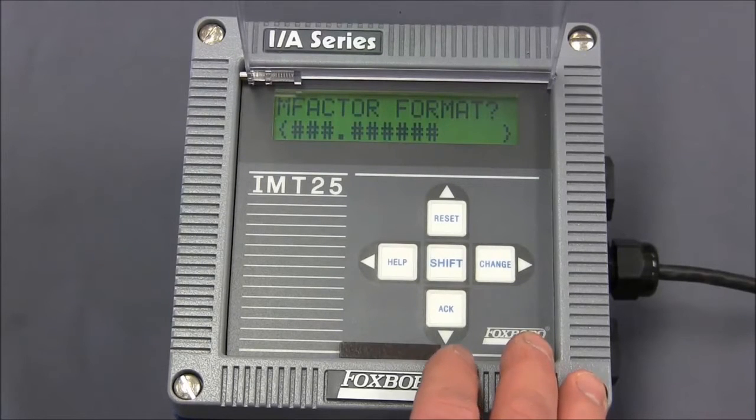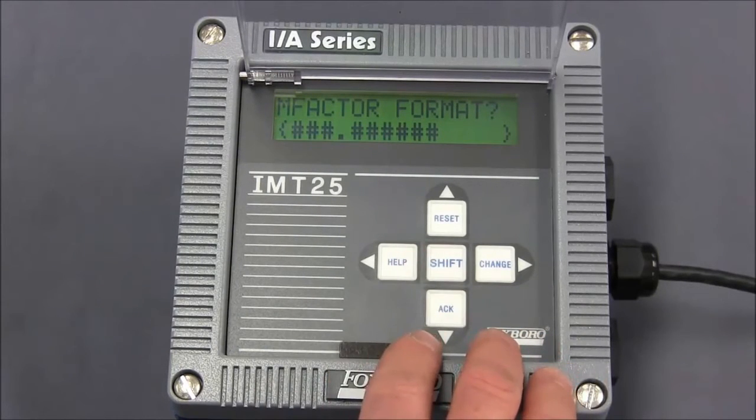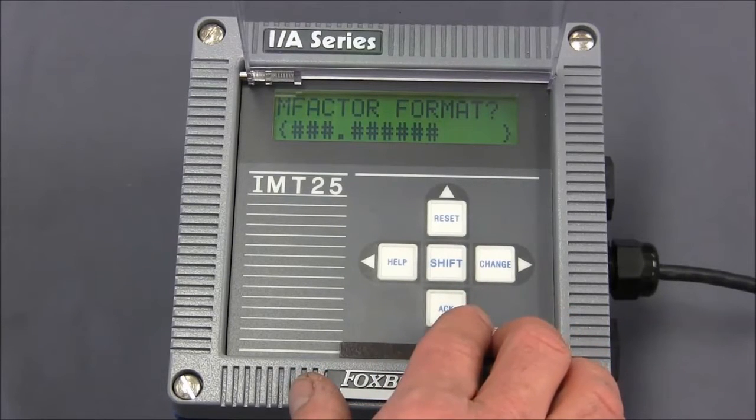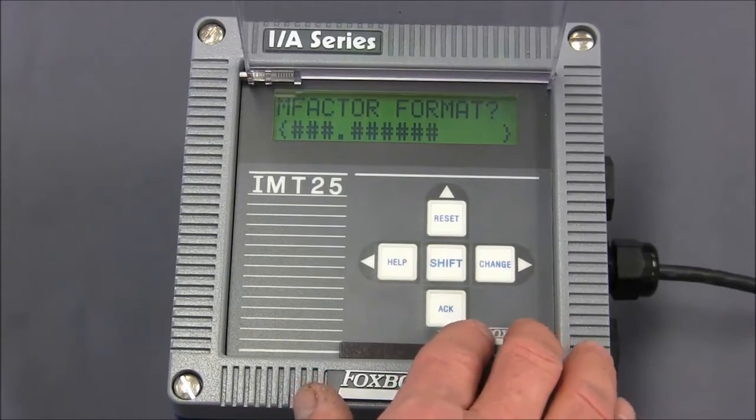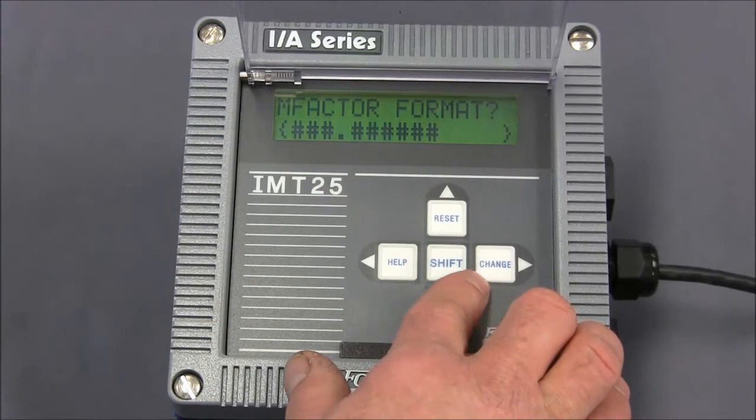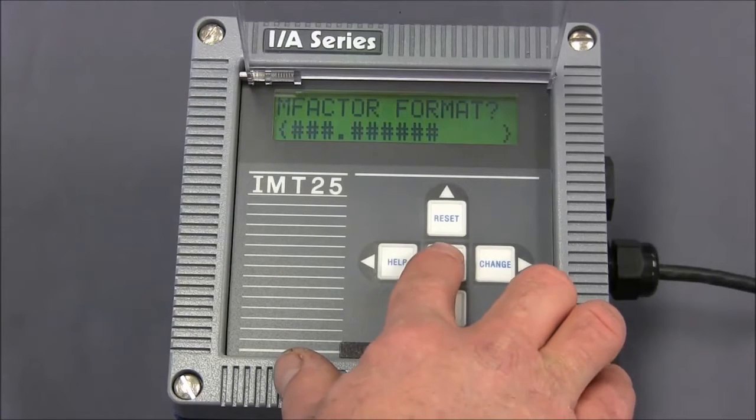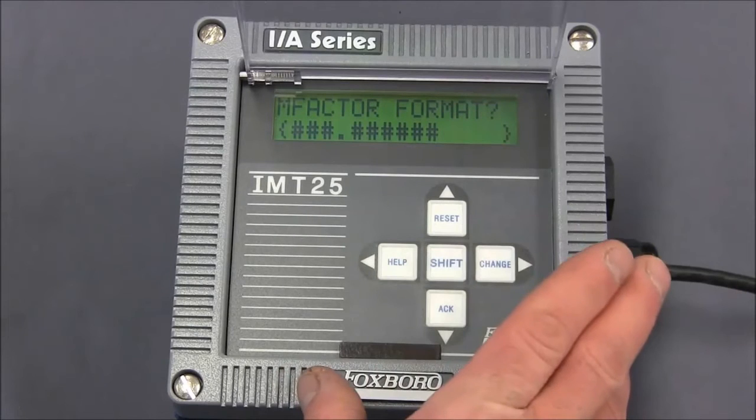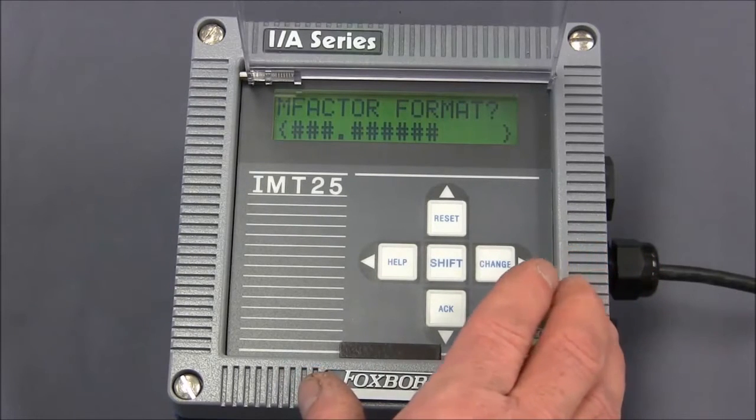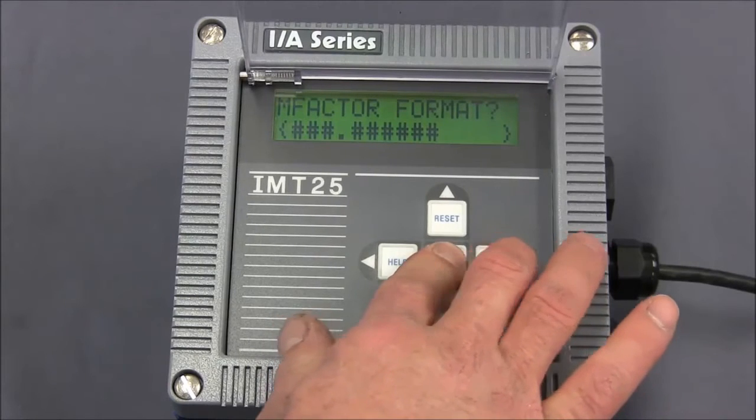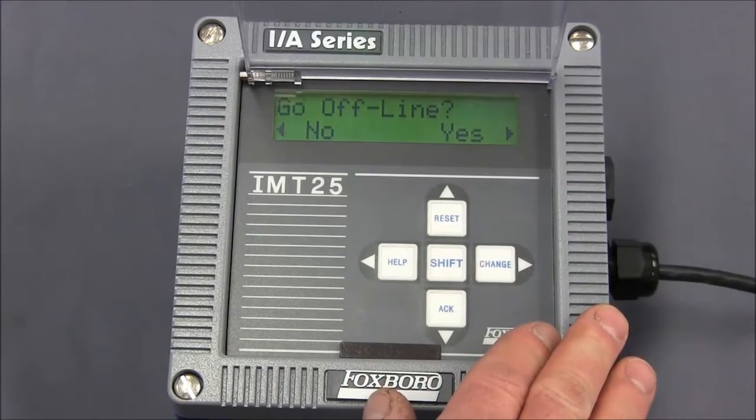To do this, to get the instrument into edit mode, there's a two-button key combination we must hit, and those are the shift key and the change key. I usually recommend pressing and holding the shift key, pressing the change key, and then releasing both buttons together. So we're going to press and hold the shift key, press the change key, and release them both together.